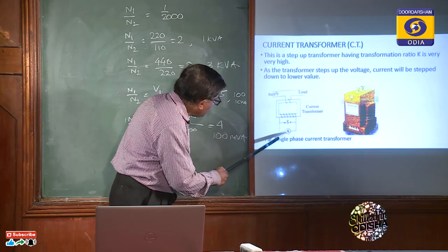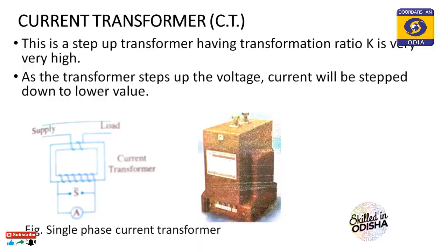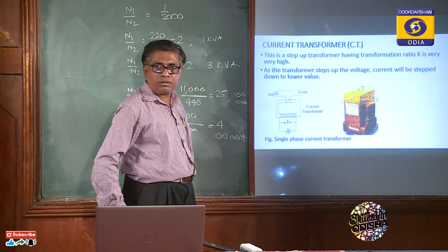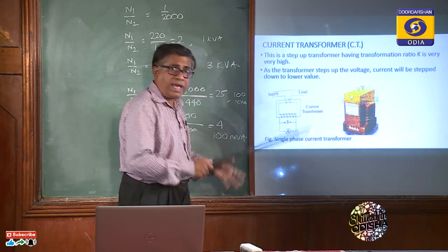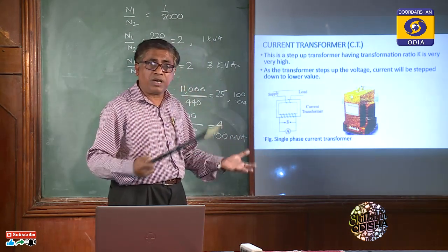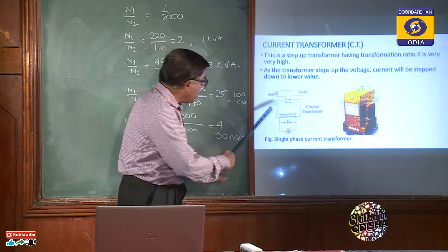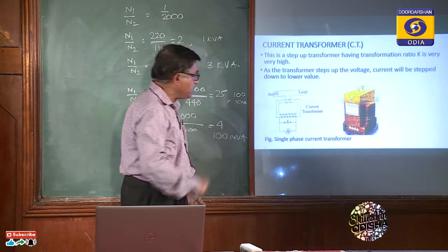If in daytime the ammeter is showing 0.5 ampere, so actually what is the current? Now this current is 1000 ampere. Actually we have to take the reading from this ammeter, then we have to use the conversion. What is the conversion? Now 1:2000. This is the work of the CT.